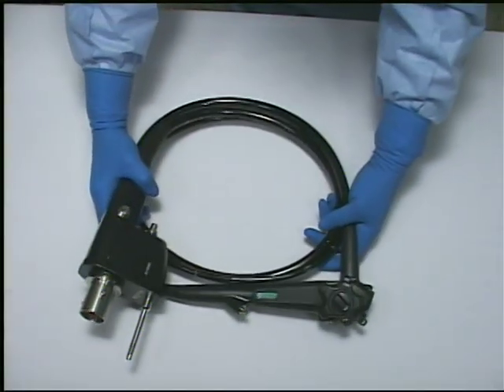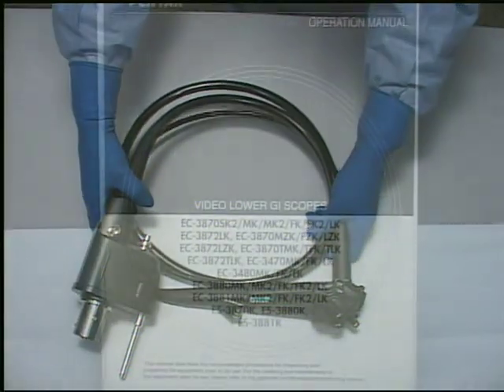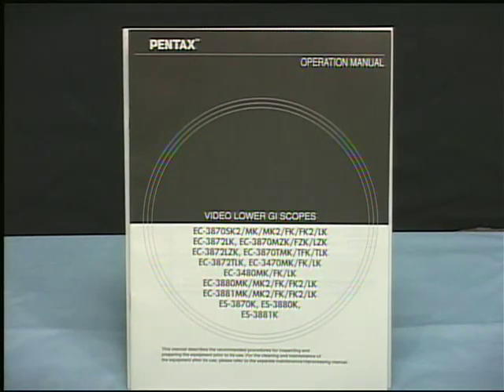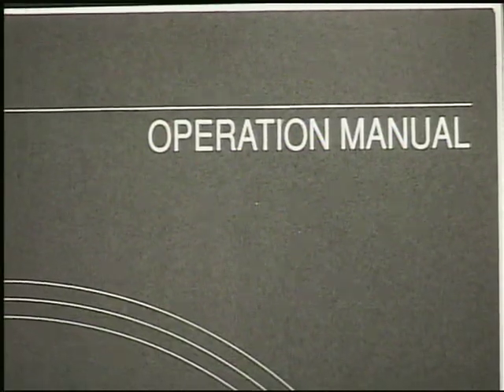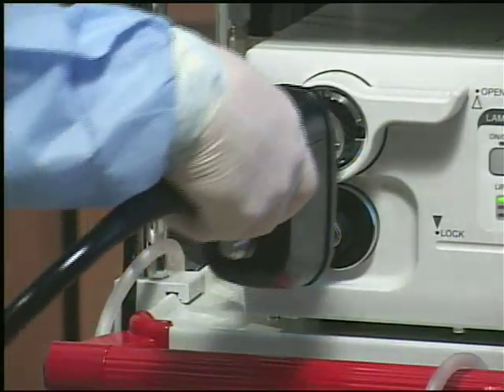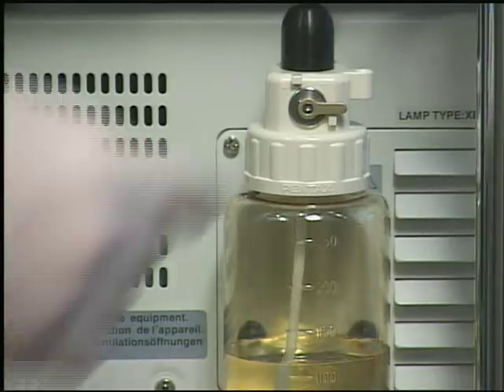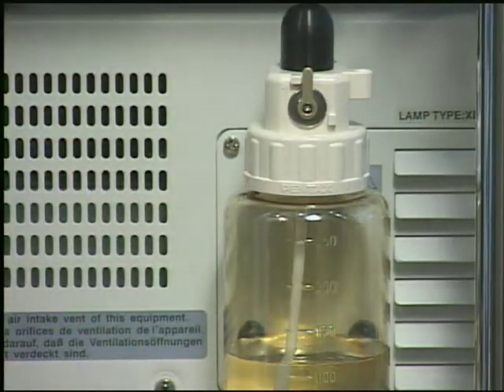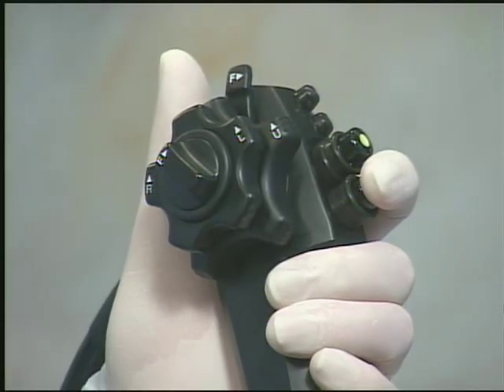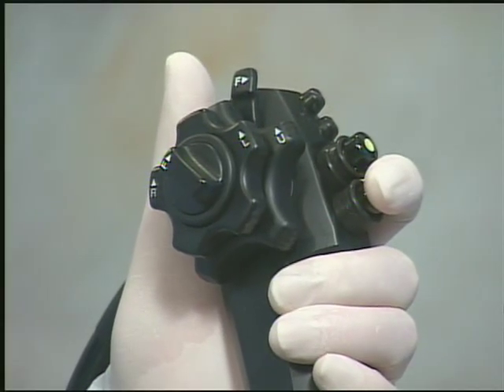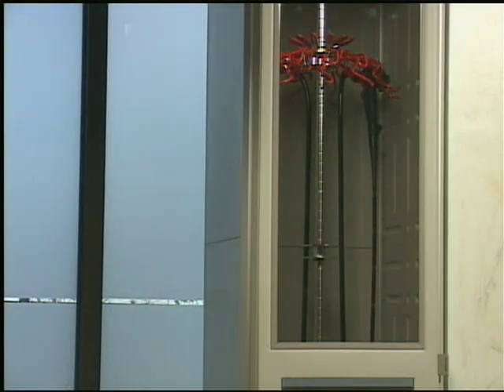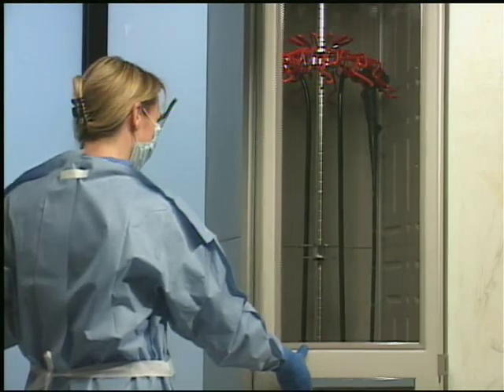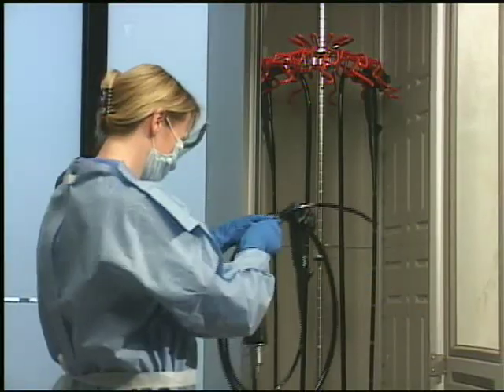Post-disinfection. If for immediate reuse, ensure that the instrument has been properly inspected and fully prepared for the next clinical procedure as per the instructions found in the Pentax operation manual supplied with each instrument. During testing or inspection of individual scope functions, such as air, water, and suction, use only sterile or fresh distilled water. If the endoscope is to be stored, ensure that all internal channels are completely dry.